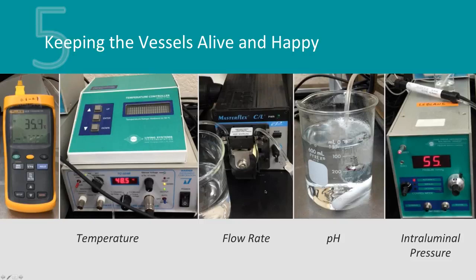Keep in mind that if you're pumping fluid in, you've got to remove fluid from the bath. You can do that if your lab is equipped with house vacuum. You can attach a vacuum flask to the end of your chamber on the outflow side and remove it that way. Or if you don't have access to house vacuum, you can use another pump. Just make sure that the flow rate coming out is greater than the flow rate going in. One of the worst disasters you can have is if you overflow your chamber and get all that salt solution down into your microscope, then you might have to pay somebody to come out and repair and clean your microscope, and we like to avoid that.